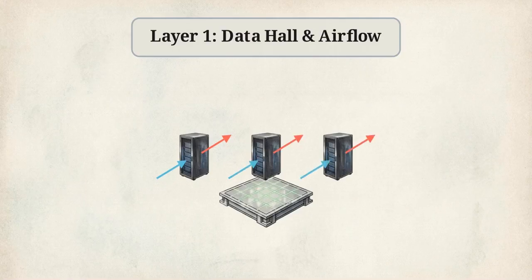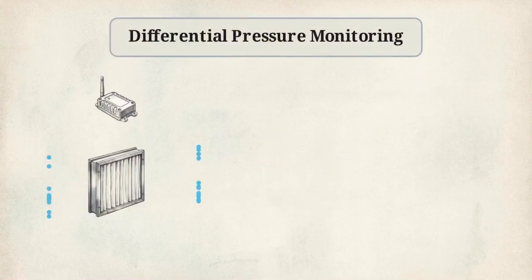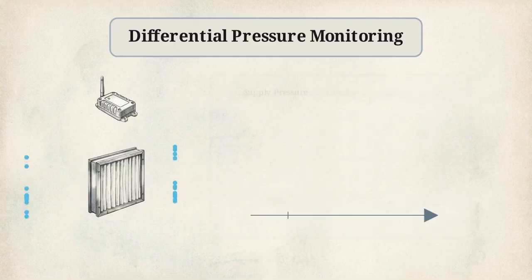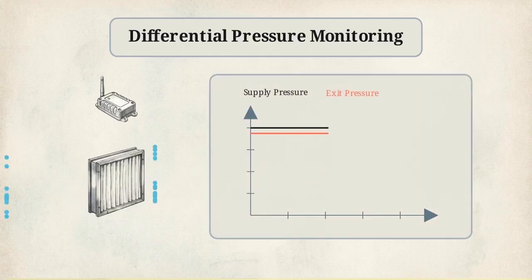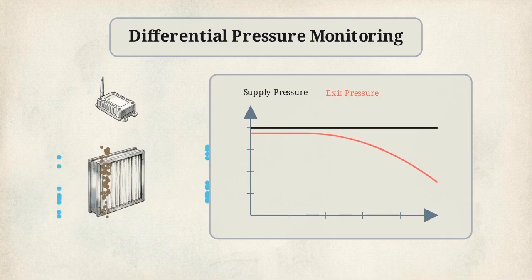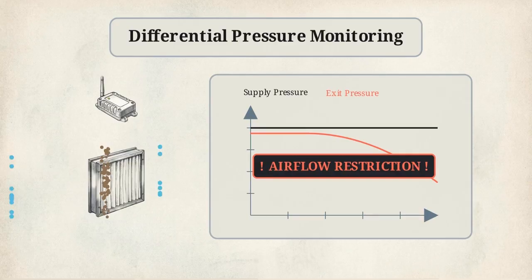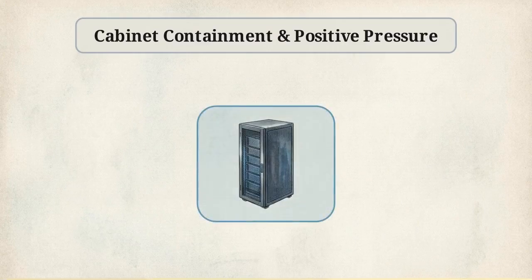High-density cooling is about precise flow vectors. Cold air must be forced into specific intakes, and hot air must be extracted through specific exhausts. Measuring the ambient room temperature tells an operator nothing about how well that air is moving. To verify that cooling is actually being delivered, operators measure differential pressure across the delivery mechanisms. This chart shows the pressure difference across an air handling unit filter. As dust accumulates over time, the resistance rises and the pressure drops on the exit side. This metric provides an early, mathematical warning of airflow restriction.